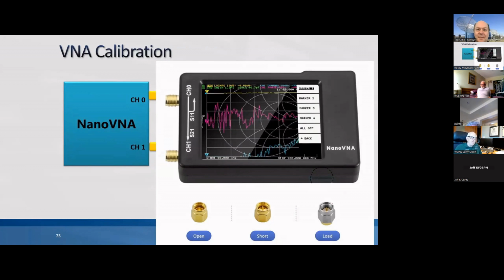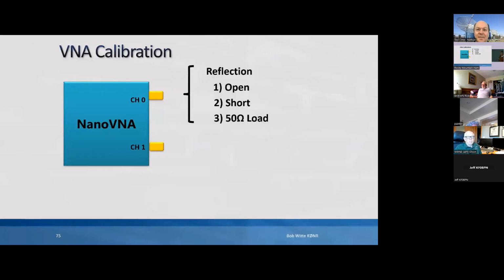A short is going to be a short, zero ohms. And an open's kind of funny, because you go, why do I need an open? Can't I just leave the connector off? Yeah, you probably can. But what the open does is give a more controlled open impedance that makes for a better cal. So it's a calibrated open, because if you just open a connector, what do you really have there? But if you put the calibrated open on, you know exactly what's at that port. So those come with it.